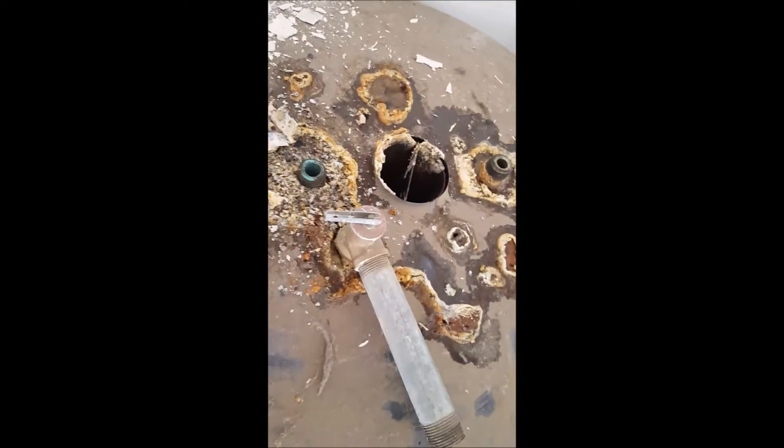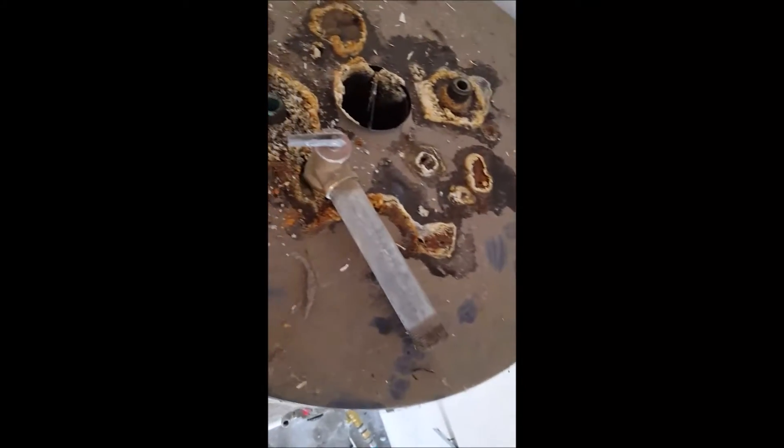The cold line's not so bad — it'll be replaced anyways, but it was starting to go. Worst part is the top of the tank. You can see quite a bit of problems going on here. Several spots on the top of the tank were blown through and leaking, and that just leaked down inside the tank as well as outside the tank and down to the platform.